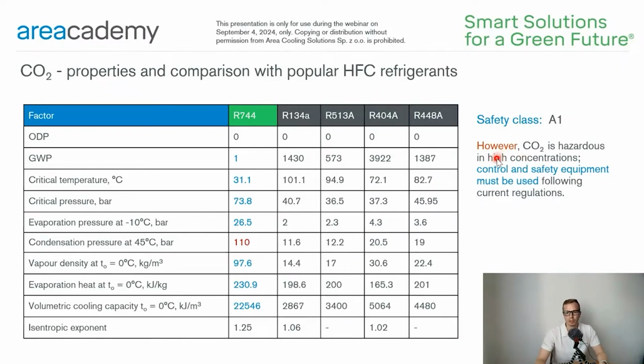So now we know that indeed CO2 has valuable advantages. Now let's look at the parameter values compared to the popular HFC refrigerants. We have here, for example, the R513A. It is an azeotropic mixture as a replacement for the R134A. And azeotropic means there is no glide of temperature. And there is also R448A. This is a zeotropic mixture as a substitute for 404A refrigerant.